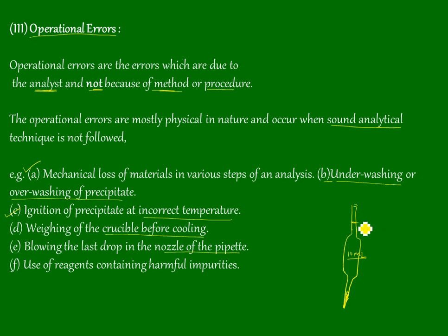This 10 ml pipette is calibrated by excluding the last drop. So this drop is not considered in this 10 ml pipette. That means you should not take this last drop. You should not blow.